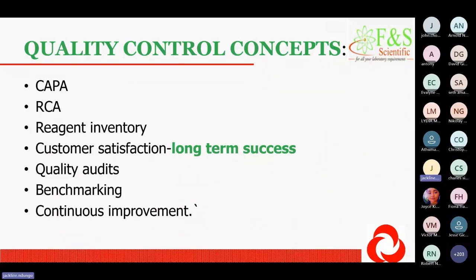What are some of the concepts in terms of quality control? Once your control has failed, you raise something called corrective action. And it's also important that you do preventive action. As much as you have corrected the error, you need to look at what is going to prevent future recurrence. This can be done in several ways. There's a slide that I have presented in terms of the fishbone, that can either lie under CAPA or under root cause analysis. So with root cause analysis, you're just trying to look at what is the cause of this mess, and you can use the 5 Whys, you can also use the fishbone. All these things, if you're not so much used to them, you can just go find out from the resources that we will have given, and also just Googling around. It will give you a lot of information.